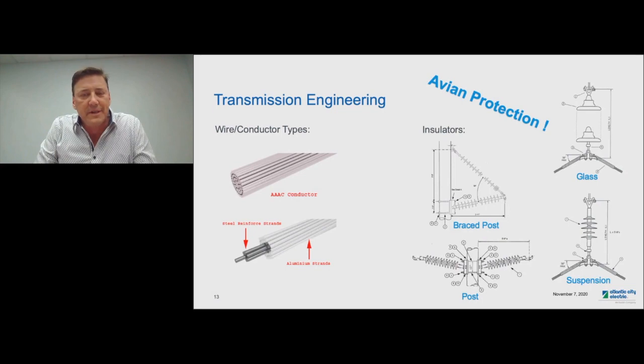At the top of the pole, the reason we put the pole in the air is the conductor. There are two broadly used types of conductors for transmission. The all-aluminum conductor, seen at the top left, carries a lot of current, but one of the challenges is the physical strength of the wire. To meet the loading requirements, which is not atypical for our service territory, we used an aluminum conductor with steel reinforcement, allowing it to hold up to stronger winds and potential flying debris. On the right, you see the brace post and post insulators, which is how we attach to the pole.